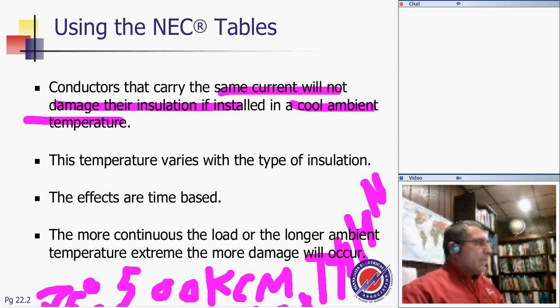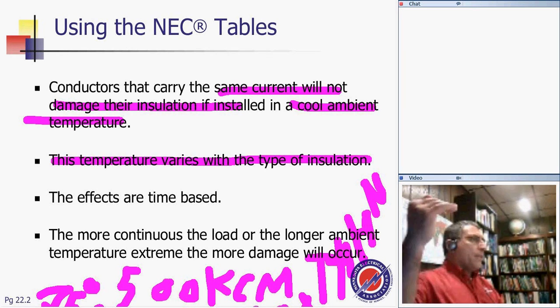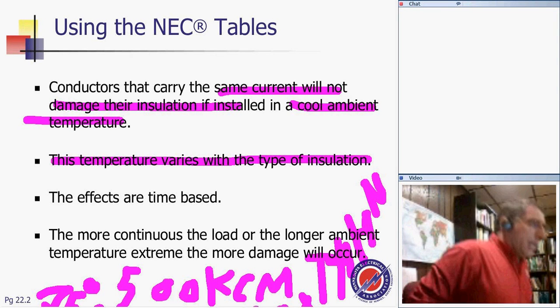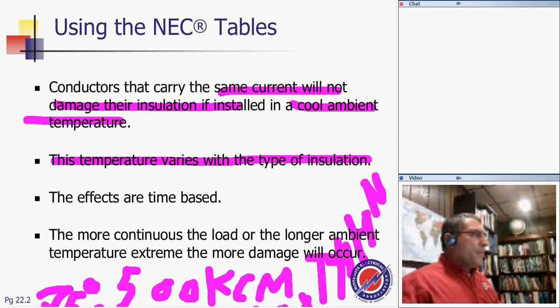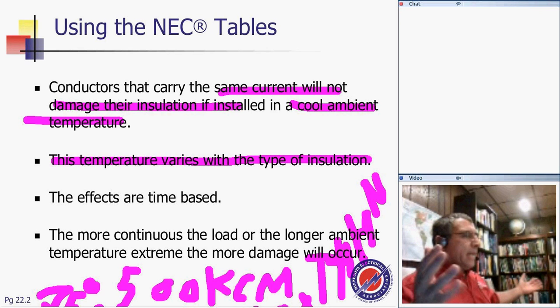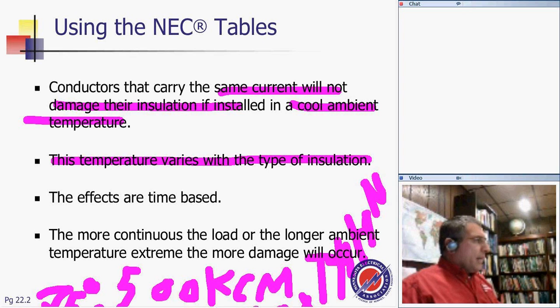Again, the conductor can carry more current if the temperature is low. Why? Because if the temperature is low, guys, the effect of heating on the conductor is not going to be as substantial as if the ambient temperature is high. If the ambient temperature is high and you're heating the conductor, it will reach a melting point much sooner than if it was in a freezer. How long you leave the conductor hot, the time is a big deal, guys. Also, with continuous load or longer exposure to extreme ambient temperature, more damage will occur. So if you put continuous load in an extreme temperature, you're going to damage the insulation much more.